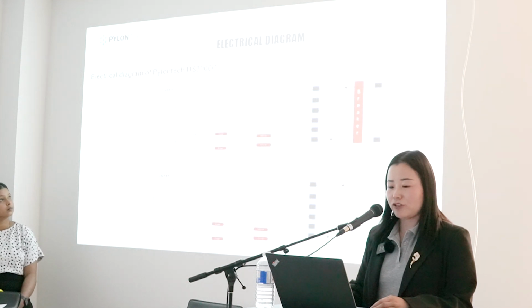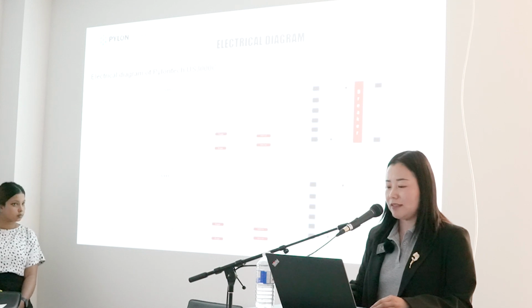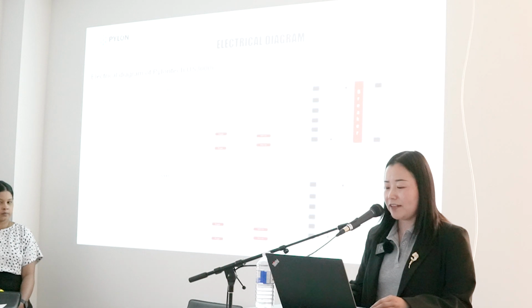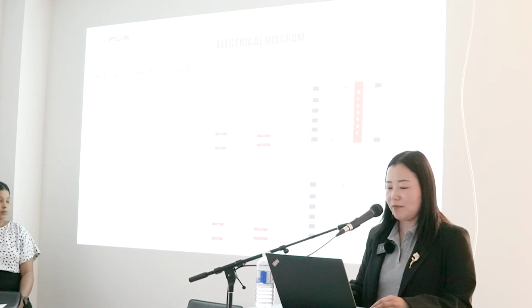Here is the electrical diagram. 2 batteries are connected in parallel. There is a breaker on the power cable. RS485 can support communication between batteries and inverters. Between batteries, we use CAN communication. We separated the BMS board into 2 parts, one is CMU, another one is PMU. The CMU is responsible for communication and data logging, and the PMU is responsible for battery control and protection.